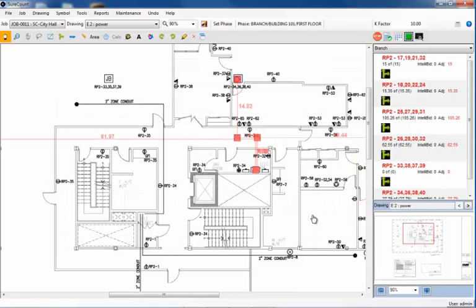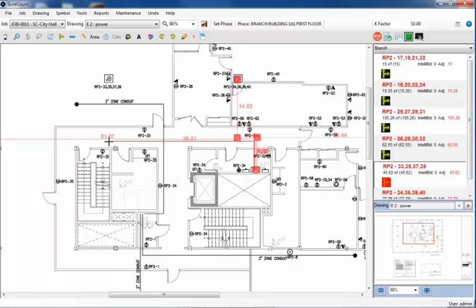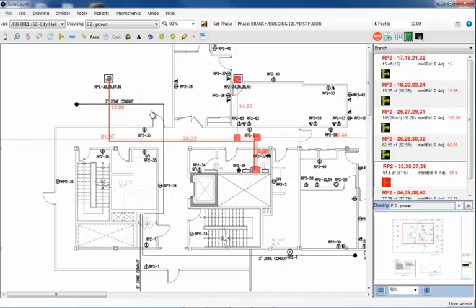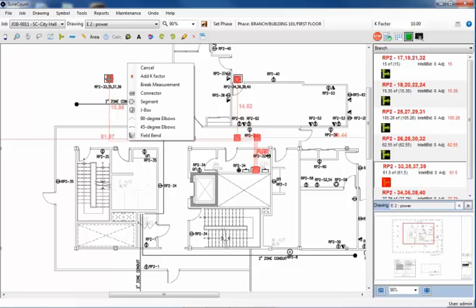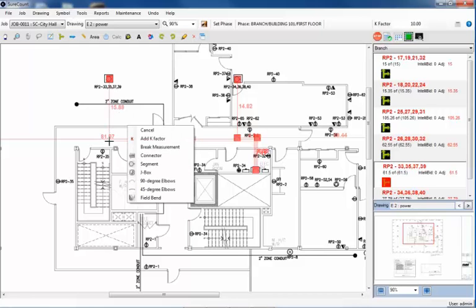I'll select the branch. With the crosshairs, I'll begin at the panel RP2. I'll left-click the mouse, come out to the hallway, and left-click again. Straight over to the left, and I'll left-click again. Then, up to the junction box, and I'll left-click. At the junction box, I'll right-click the mouse, select a junction box from the list. I'll right-click the mouse again, and add a segment. Then, come straight down at the bend, and I'll right-click again, and add an elbow. Over to the right, I'll right-click again, and add a field bend. At the top of the panel, I will right-click, and add another elbow.